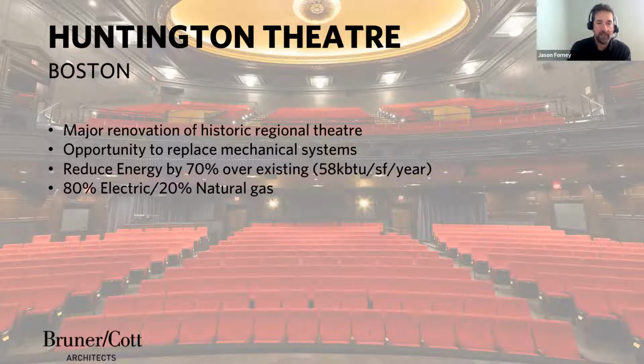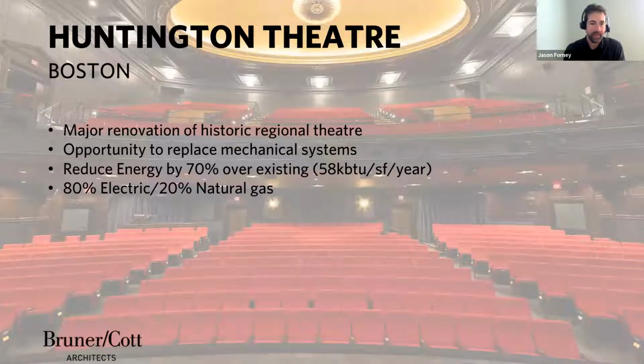The outcome here, and this is still a prediction through an energy model, is that we were able to reduce the energy use of the building by over 70% compared to its existing state, which is about 50 kBTU per square foot a year. Within that, we achieved 80% of energy sources being electric and 20% natural gas. Now, we wanted to go for 100% electric, but there were some challenges that we decided to back off of, while leaving room for conversions over time of that last 20%.